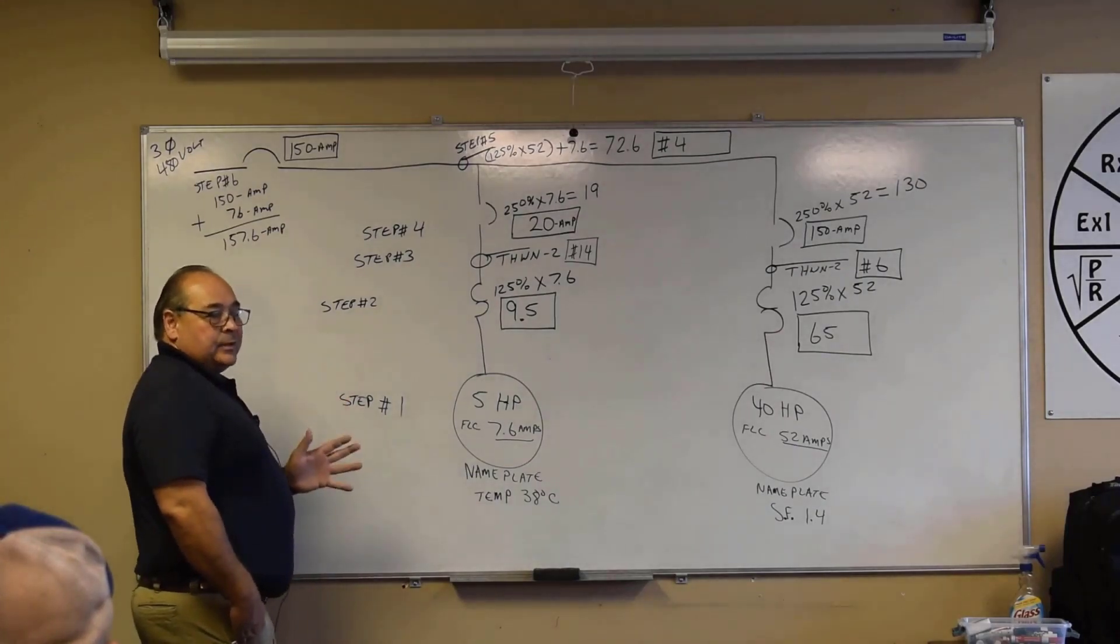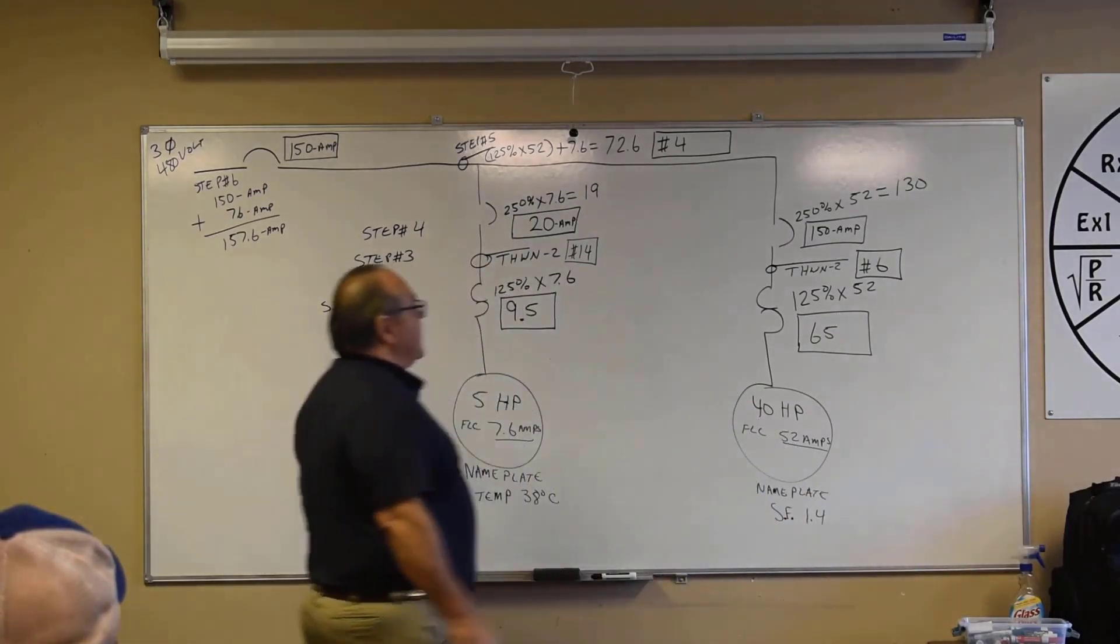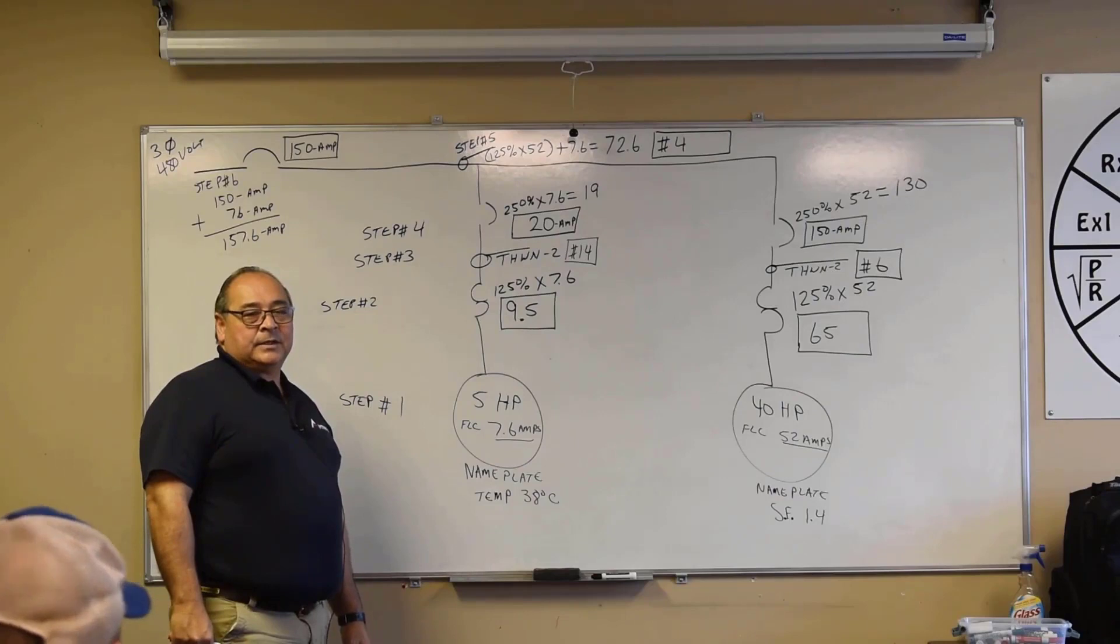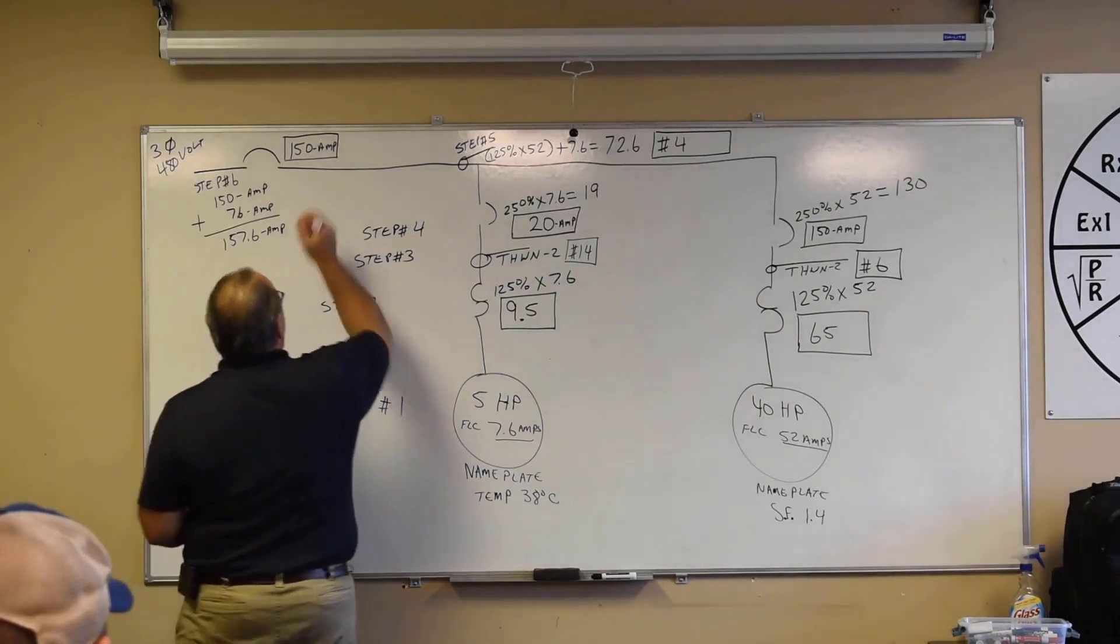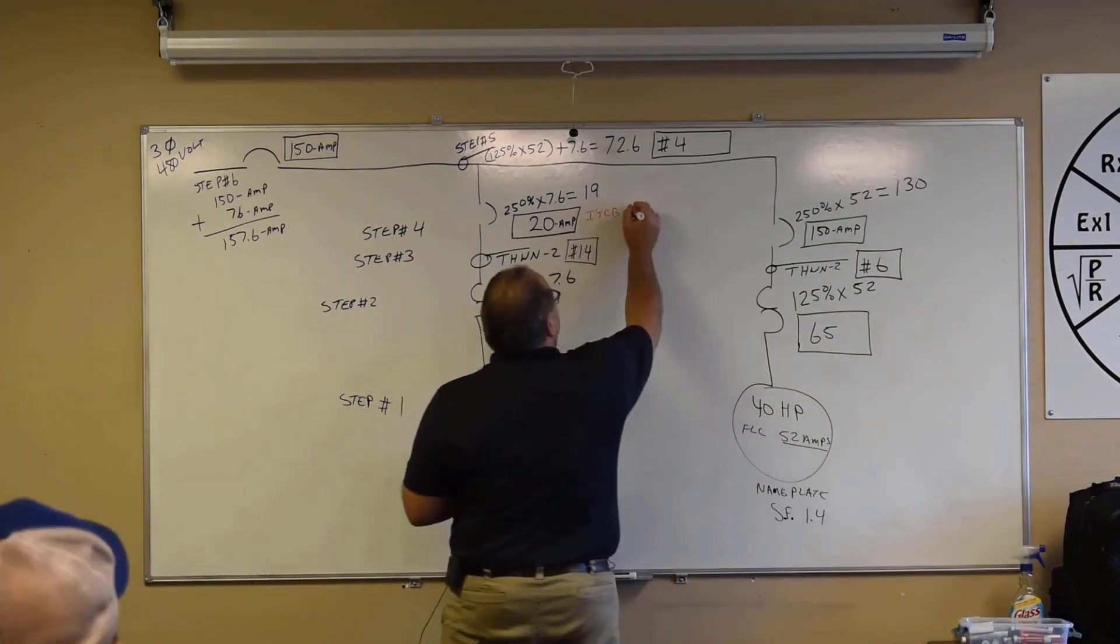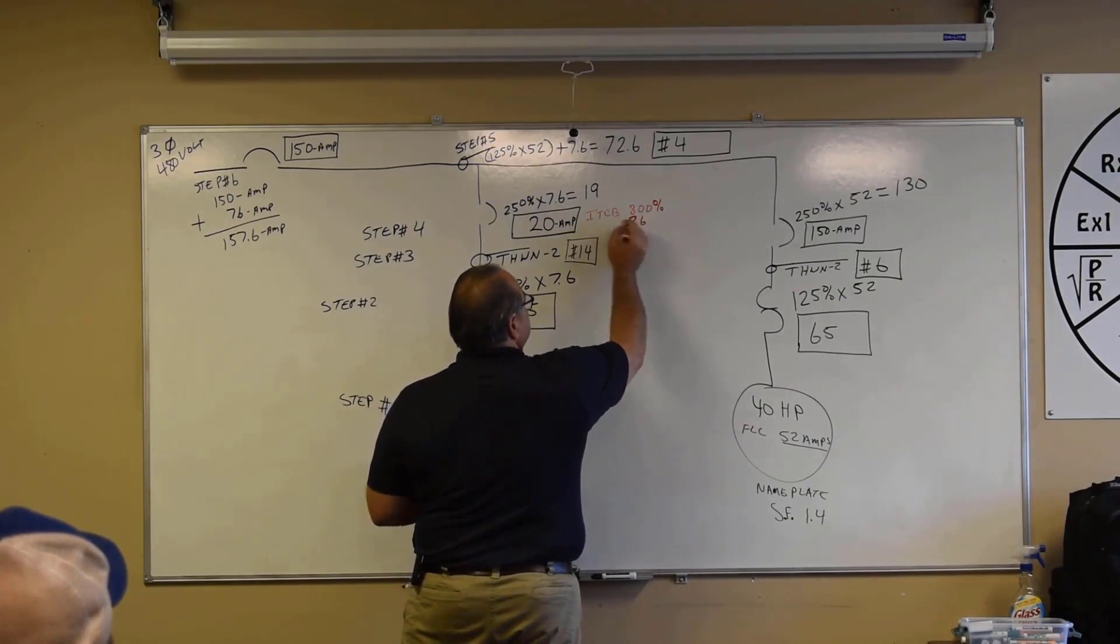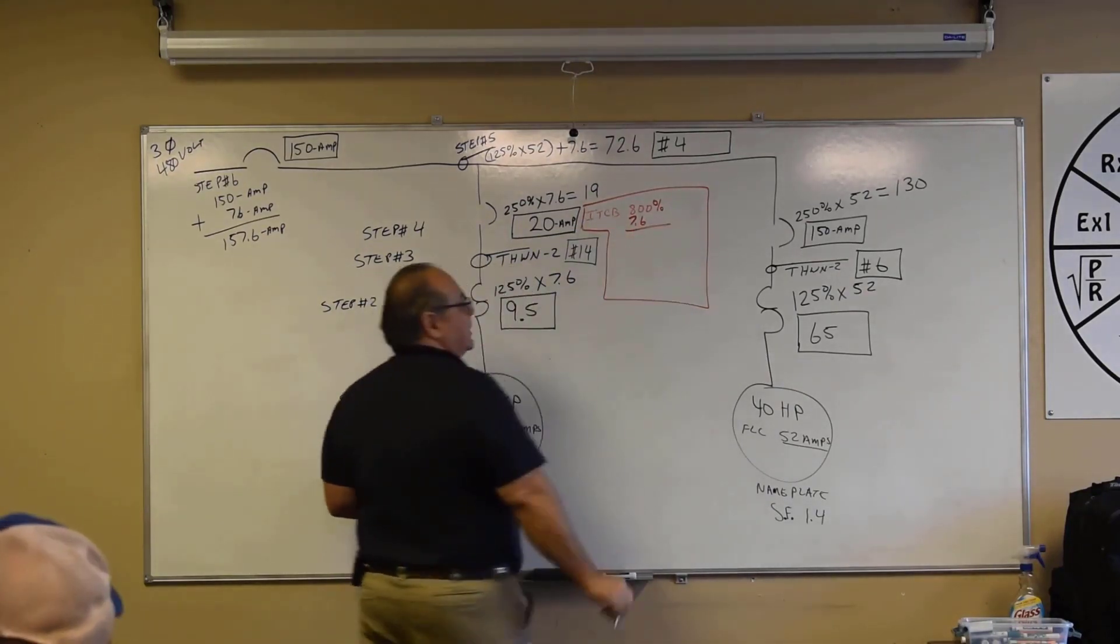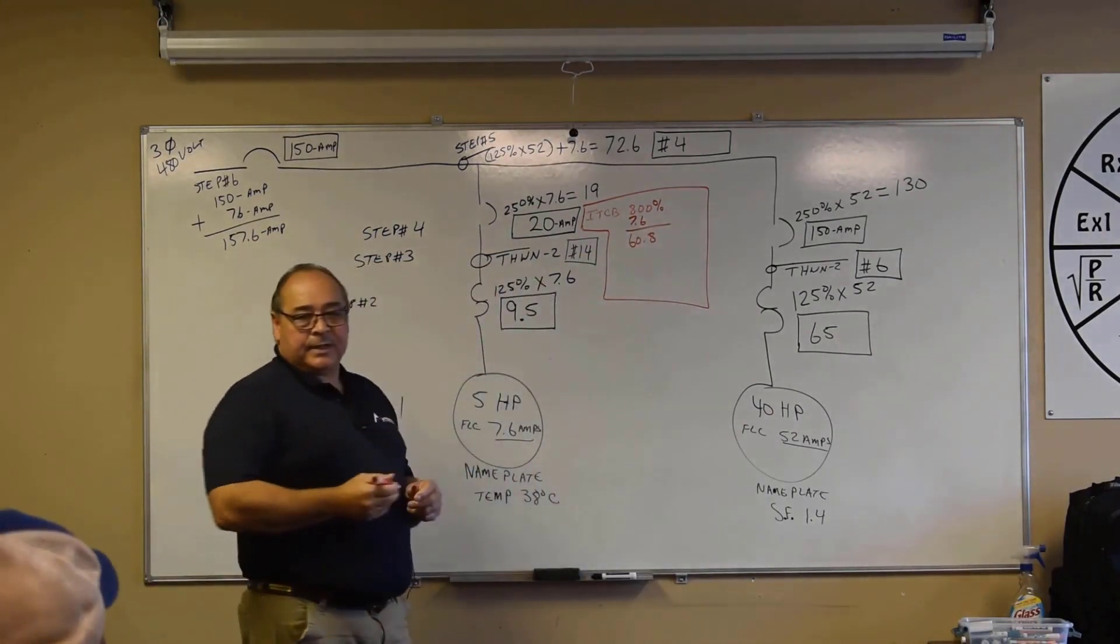I'm going to change one parameter and show you how extreme this can be. Instead of using that inverse time circuit breaker, change one parameter, we're going to use an instantaneous trip circuit breaker. What's the percentage for an instantaneous trip circuit breaker? So we're just going to change one thing. And let's start right here. So for instantaneous trip circuit breaker, it'll be 800 percent. So 800 percent of what? The 7.6. So we'll make this little breakout right here just to kind of get us understanding here. What's 800 times 7.6? 60.8. And we're allowed to go up. 60.8 is not a standard size, so I go up, right? Okay, it'll be a 70 amp.